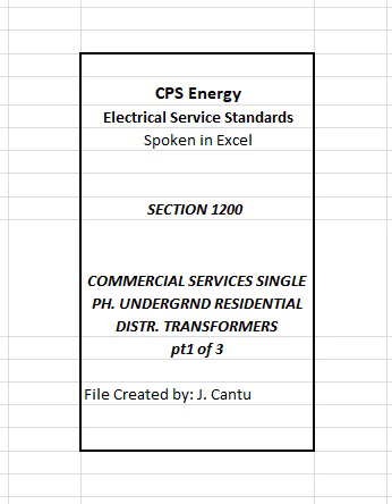1201-3 Transformer located on customer property. A. New transformer. Where a new URD transformer is to be installed, the primary distribution will be installed in accordance with Article 1204 and the service will be installed in accordance with Article 1205 and Figure 1201, A, B. Note 1. Review and approval shall be obtained from the customer service representative to determine the interconnection to the existing distribution system. Note 2. Property owners seeking to replat their property will be required to contact their CPS Energy customer service representative for a separate service.